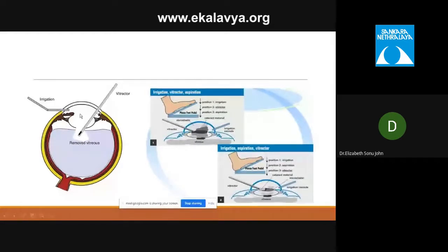And this is the foot pedal, like I said, for cut IA and IA cut. So this is irrigation, vitrectomy, and then aspiration, which is used for vitrectomy. So your foot pedal in position 1 is irrigation. Then when you go down, it's in vitrectomy, and then in 3 it is aspiration. And the other way around for...